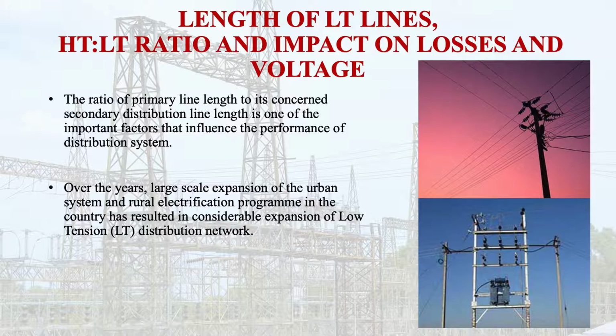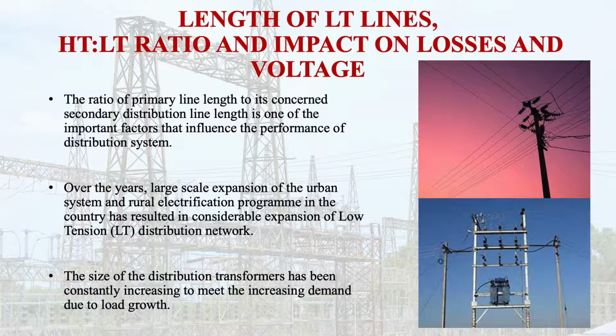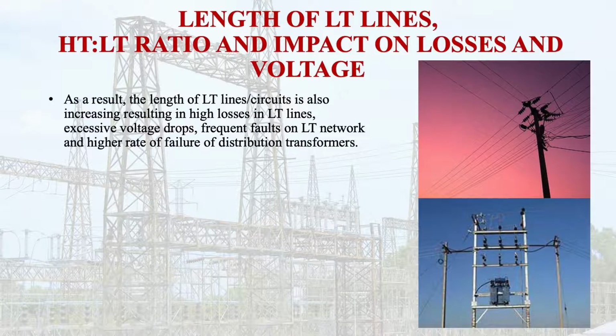Now, over the years, large-scale expansion of urban systems and the rural electrification program in the country has resulted in considerable expansion of the low-tension distribution network. So the size of distribution transformers has been constantly increasing to meet the increasing demand due to load growth. As a result, the length of the LT lines per circuit is also increasing, resulting in high losses in the LT lines. That means if the length of the LT lines is more, there will be high losses. We have already discussed all these things in our previous sessions. Then excessive voltage drop will be there if there are high losses. So frequent faults on the LT network and a higher rate of failure of distribution transformers will happen.